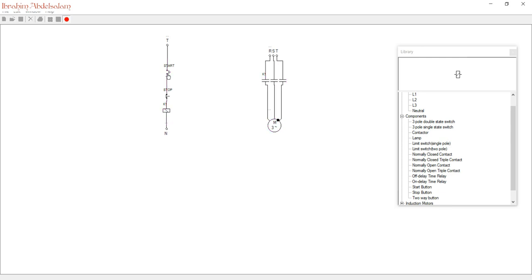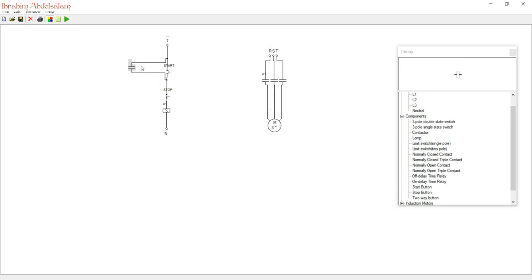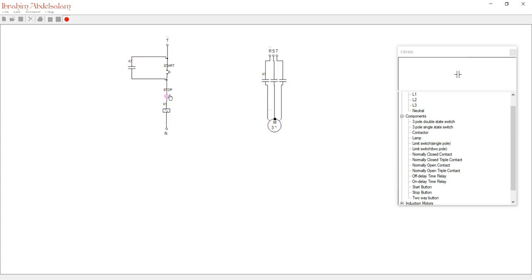Let's run the simulation. I press start — the motor is running. If I remove my hand from start, the motor stops because we didn't add the latch. You can see that once I release my hand, the current doesn't find an auxiliary path. So I stop the simulation and add our auxiliary contact — a normally open contact. I rotate and connect it, and attach it to K1. Let's run again. Press start — the motor is running. I remove my hand and the current finds another path through the auxiliary contact. The only way to stop the motor now is to press stop, which interrupts the current flow.